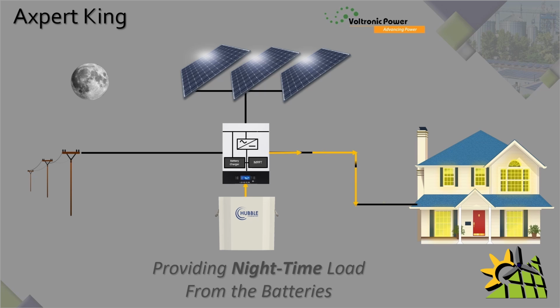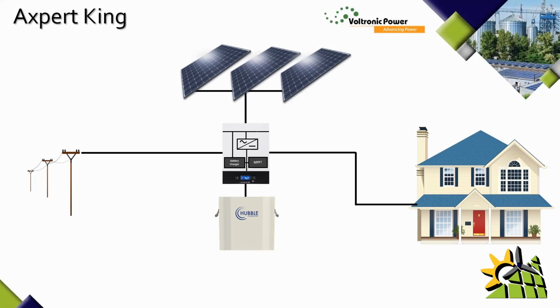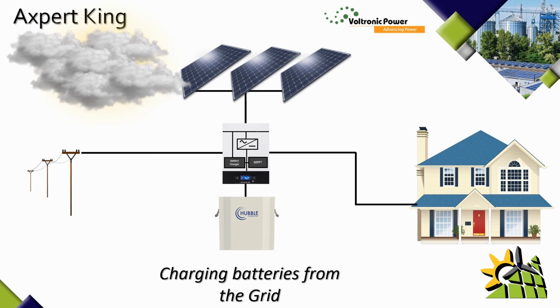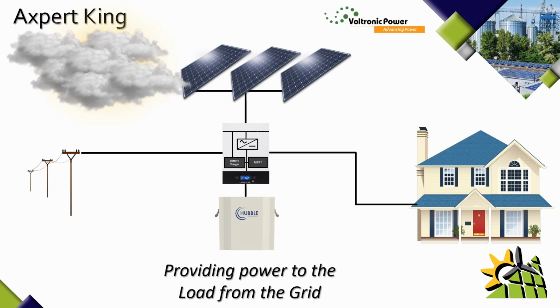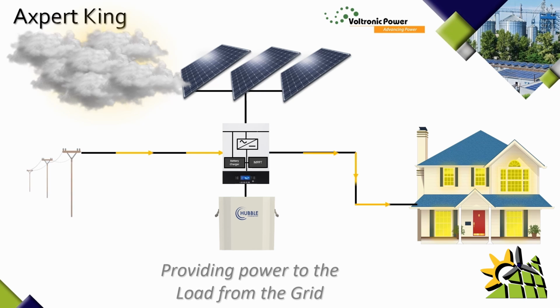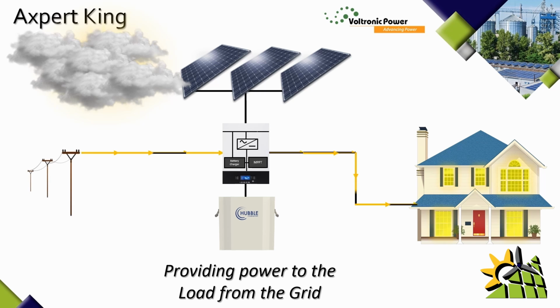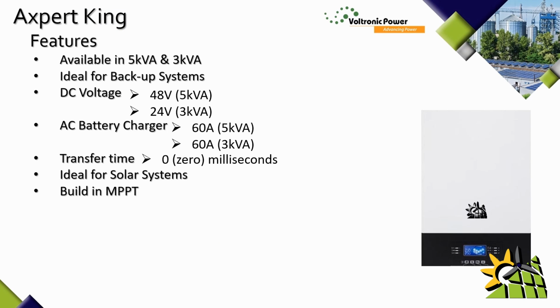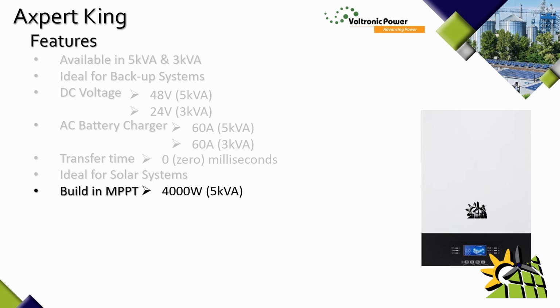Now, the grid connection will still be available, but this will only be necessary during cloudy or rainy days, where there's not enough sunshine to charge the batteries. In this instance, you can use the grid to charge your batteries. The inverter would also provide power to the load from the grid during cloudy and rainy days. So the grid would only be there as a backup during cloudy or rainy days where there's not enough sunshine to provide power from the solar panels. Now the built-in MPPT controller on the Axpert King is 4 kilowatts on the 5 kilowatt inverter and 1500 watts on the 3 kilowatt inverter.